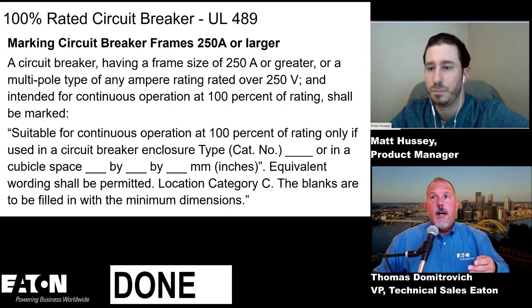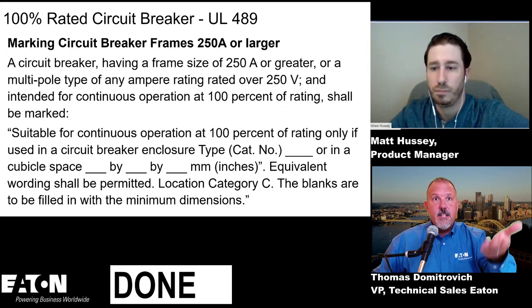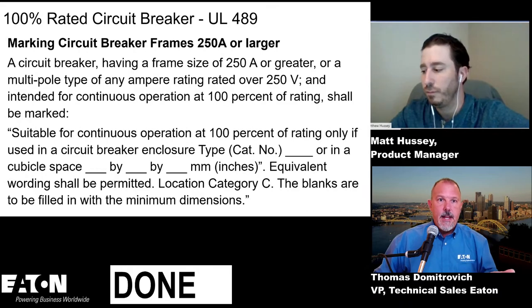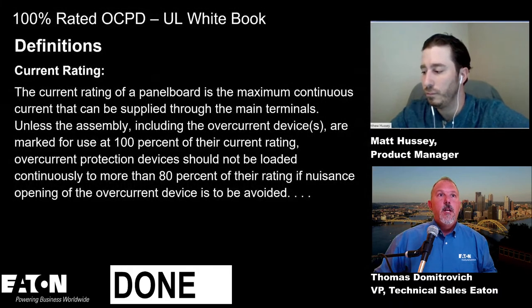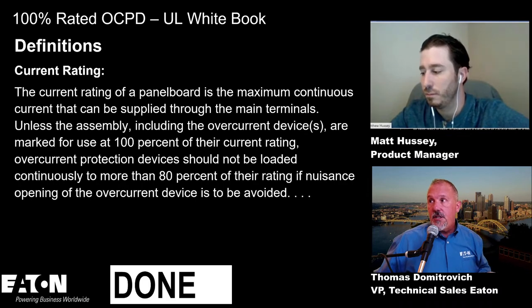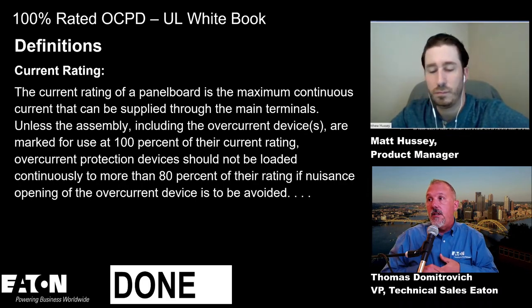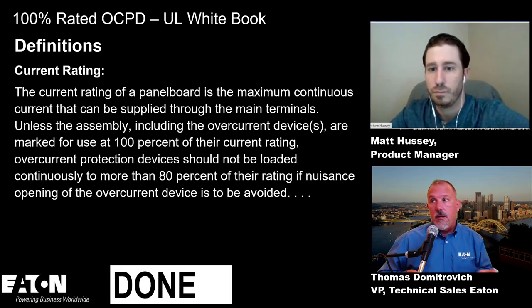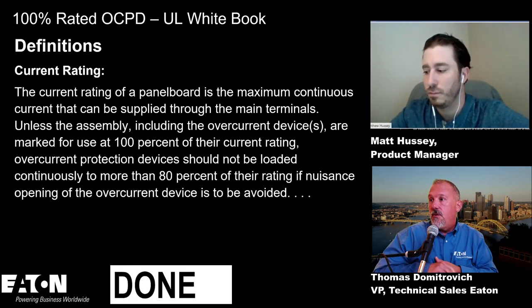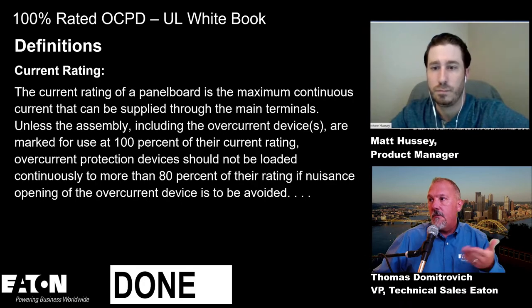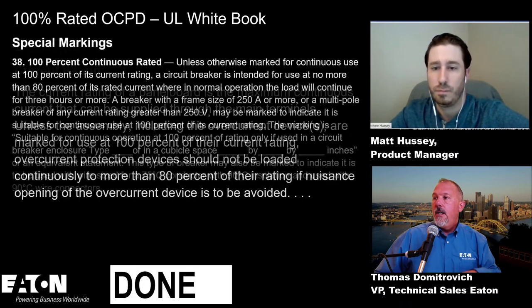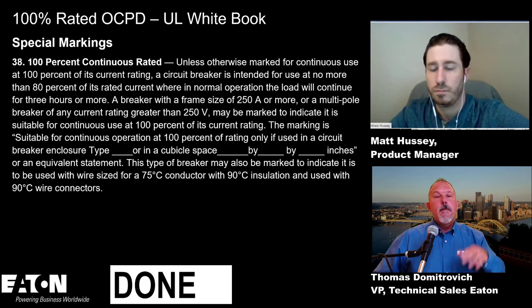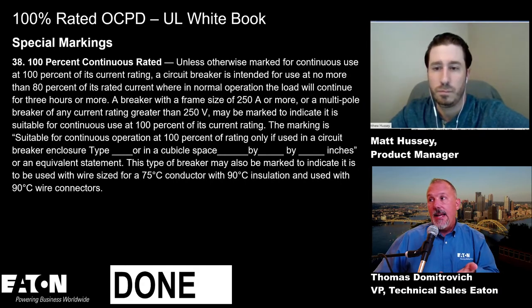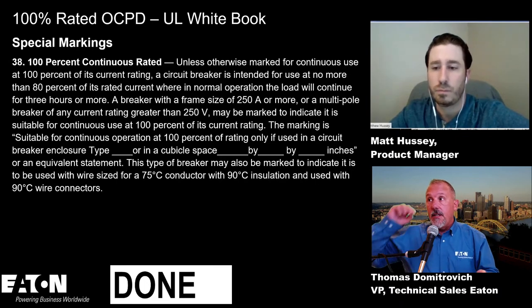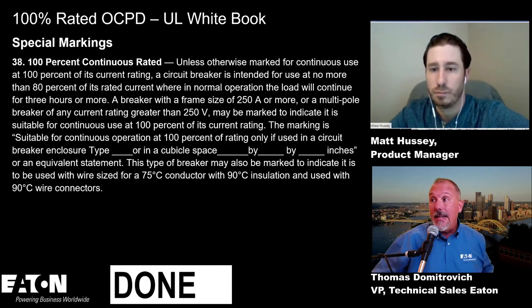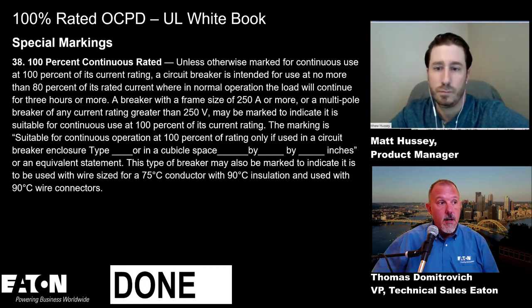Yep. So then this gets into the different size and frame ratings and how it's supposed to be labeled. There are some definitions in the UL white book that talk about the current rating of a panel board being the maximum continuous current that can be supplied through the main terminals, unless they're marked for use at 100% of their current rating. Otherwise, it's at 80%. When they are 100% rated, they tell you exactly how the equipment and the overcurrent protective devices are supposed to be labeled, and they're supposed to indicate that they are 100% rated.